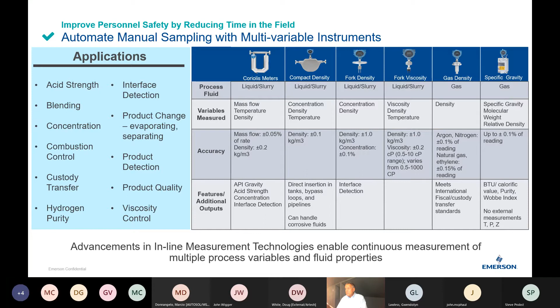All right, so let me show you a couple examples. Here's an example of one of those applications. A common thing in refining is tank dewatering. Water gets in the tanks, and then you need to drain it off. This is a lot of times done manually. You drain off the water until you get to the emulsion or the oil. We've been able to automate that procedure using Micro Motion Coriolis flow meters and density meters as well. As you let off the water and part of the emulsion, you see the change in the signal, and then can stop letting the fluid out of the tank. So that's an automated way of doing dewatering. We've got a lot of good references on this particular example. I'll show some of those at the end.